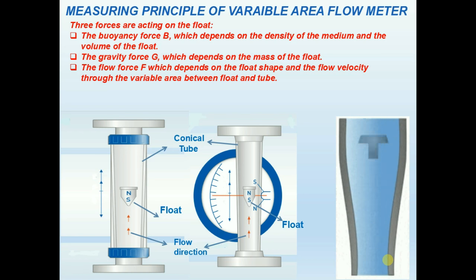The flow force F, which depends on the float shape and the flow velocity through the variable area between float and tube. So the gravity force G equals buoyancy force B plus flow force F.